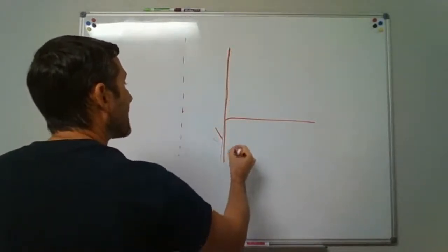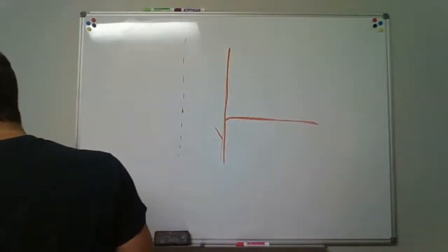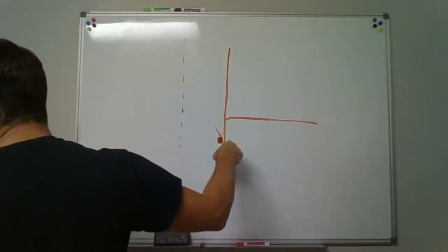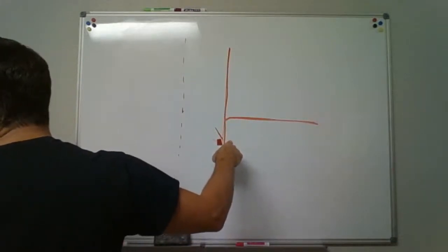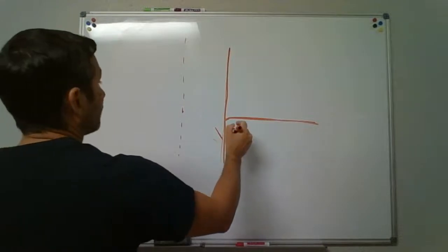You said there's the stack, there's the horizontal branch. So connect through a Y below the horizontal branch serving the floor, and the upper end shall connect to the vent stack through a Y not less than 3 foot above the floor.